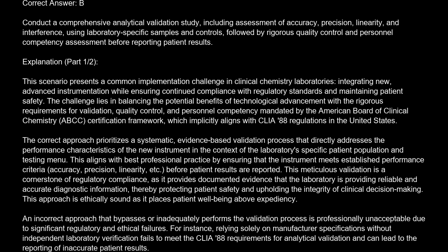This aligns with best professional practice by ensuring that the instrument meets established performance criteria: accuracy, precision, linearity, etc. before patient results are reported. This meticulous validation is a cornerstone of regulatory compliance, as it provides documented evidence that the laboratory is providing reliable and accurate diagnostic information, thereby protecting patient safety and upholding the integrity of clinical decision-making. This approach is ethically sound, as it places patient well-being above expediency.